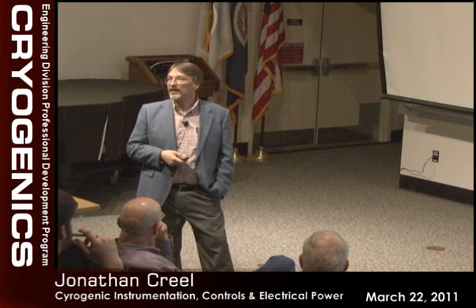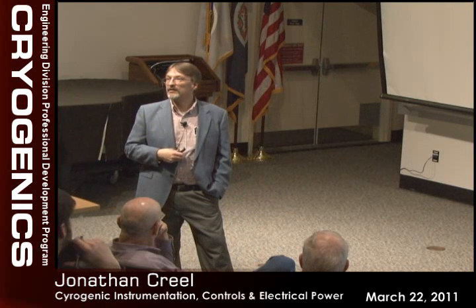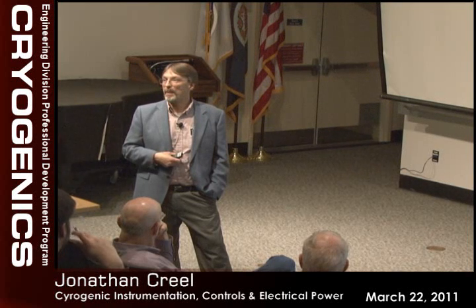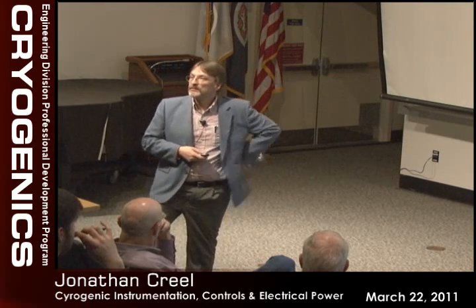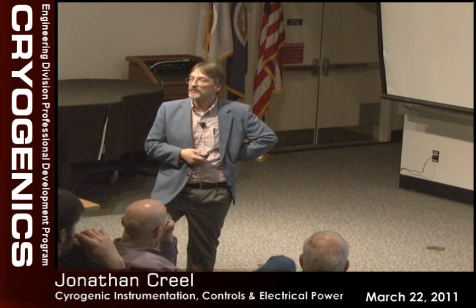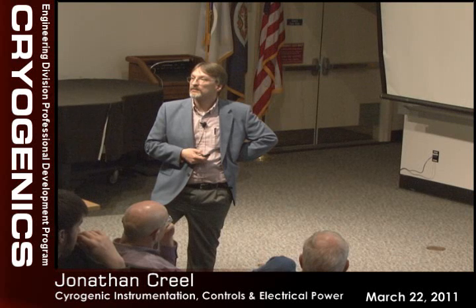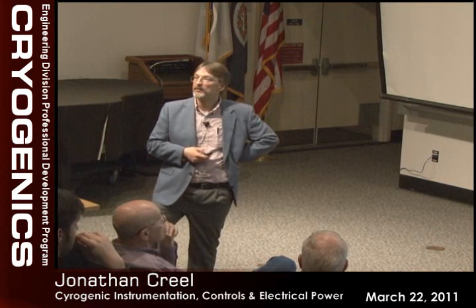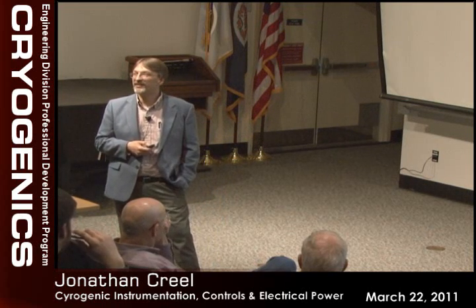The motors I put on an oil rig, we set them at a constant torque. And we shape the wave. Right. And when you do that, you basically set the power factor in a power level. And then you just grind it out, and it sits right there, and the speed will vary to maintain that torque. Right. And the power factor stays level. Right. But if you don't wave shape, you put out this radio frequency that'll set all of the radio frequencies in the area down. Airplanes and everything else.